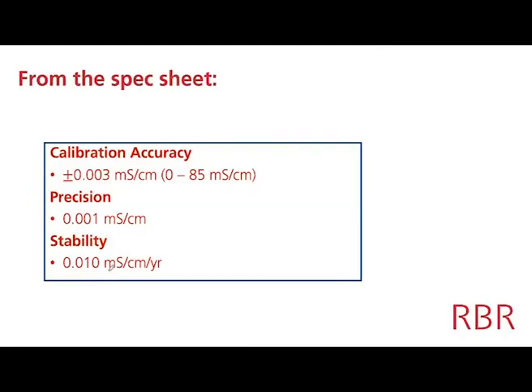All right, I'm going to move on a bit now to the accuracy, resolution, and stability of our conductivity cell. This is from the calibration perspective. We have an accuracy in conductivity of 0.003 millisiemens per centimeter. That's the same as 0.0003 Siemens per meter, if you're used to using Siemens per meter.